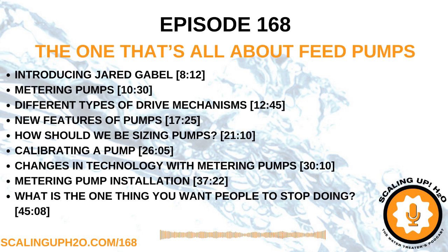It's PVDF, Kynar, for example, it's kind of a softer material. PVC and polypropylene, for example, could be more brittle and they could just crack. So be aware of that. And then always make sure, if you're actually not getting chemistry to flow through it, it could be that your check ball has maybe a piece of debris in it, or it's not been wetted properly yet to be started. And so we want to make sure that we can create that seal every time on the seat. And anytime that doesn't get done, you're not going to be able to move chemistry, because it's basically like a diaphragm and check valves have to work in unison to actually move the chemical through it.